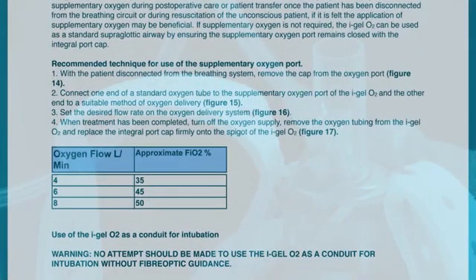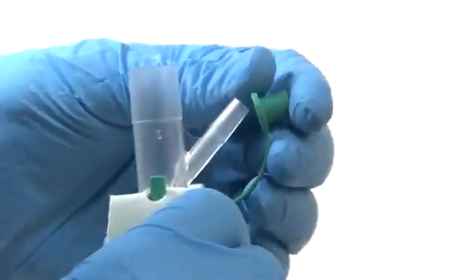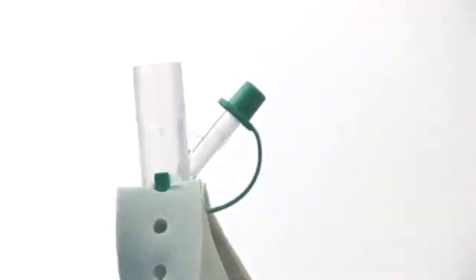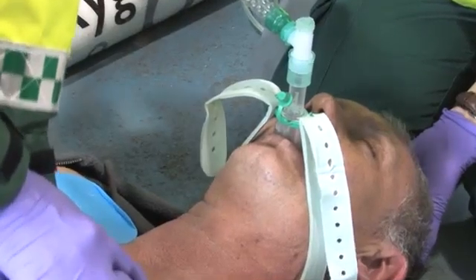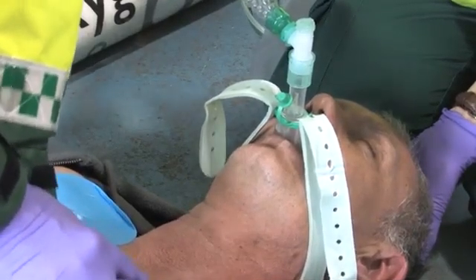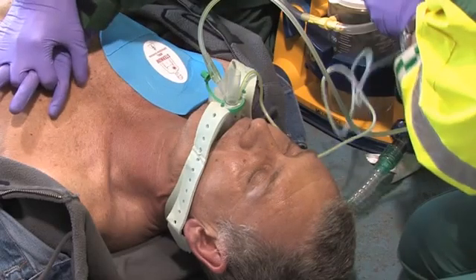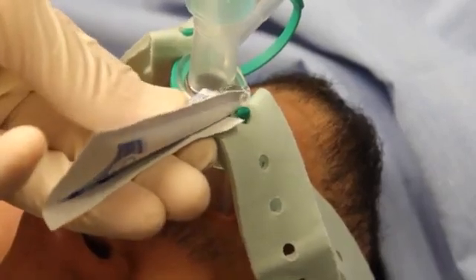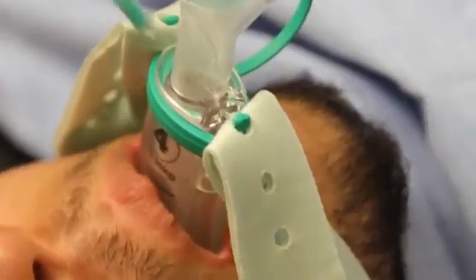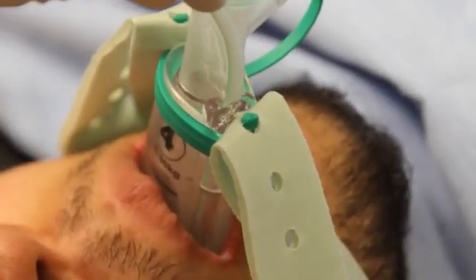When treatment has finished, turn off the oxygen supply, remove the oxygen tubing from the i-gel O2 and replace the port cap. When i-gel O2 is being used conventionally, it is important that the supplementary oxygen port remains closed. If required, a suction tube can be passed down the gastric channel to empty the stomach contents. To use the suction tube, place a small bolus of lubricant over the proximal end of the gastric channel, insert the suction tube a short way down the gastric channel and move it up and down to prime before feeding the tube down.